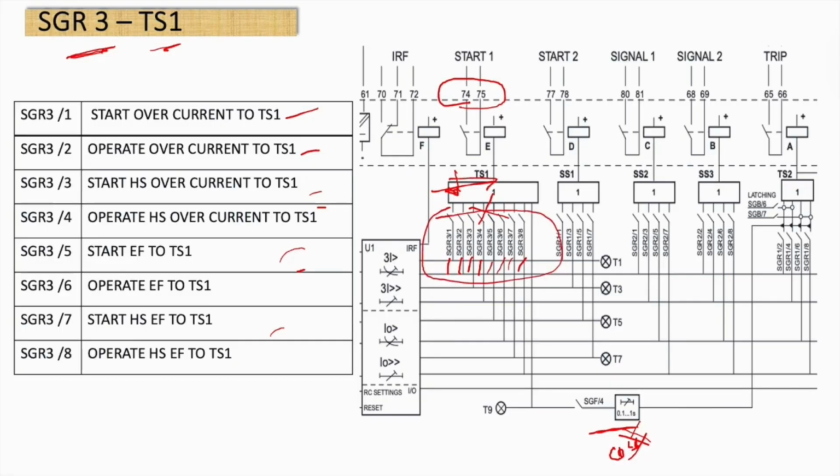So what you need to do is set them all to 1. If you only need them for tripping or operating, set them to 1 only in the operate section. Set the remaining sections to 0. Okay? Then you'll get your total, and you can see that. So TS1 is conditional. If you also use LBB, you can't do this.